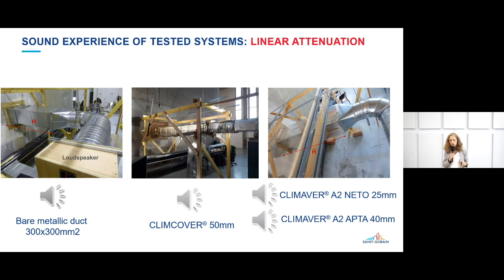Now, if we have the insulation material in contact with the airflow in the duct, like we have in CLIMAVER A2 Neto, here is what's going to happen. Okay, so I guess you heard the difference. And now if we increase the thickness of CLIMAVER A2 Neto up to 40 millimeters, which is CLIMAVER A2 APTA, then... And this was only done on a straight duct of 2.4 meters of 30 per 30 centimeters internal section. If we go back to the bare metallic duct, just so you remember.